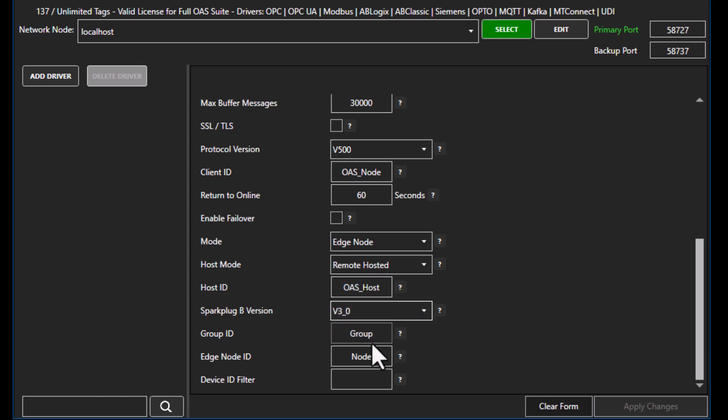The Spark Plug B version can be either 3.0 or 2.2. The group ID is important — in the next step when we define the tags to be published through this driver interface, they need to match up with the group ID. I'm going to use the letter 'A', and for the edge of network node I'll use the letter 'E'. These can be anything you'd like but must be unique. The device ID filter is optional; if left blank it includes all devices matching the group ID and edge node specified. You can also specify a specific device ID to filter to only those tags.